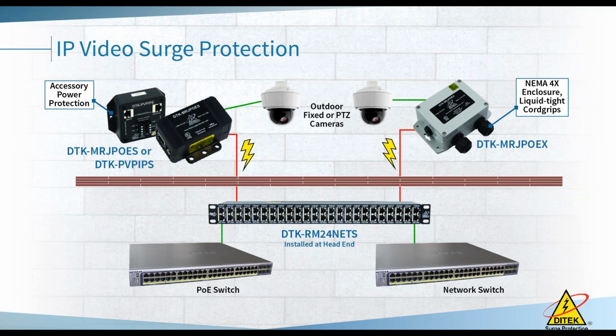The S version still accommodates plastic RJ45 and unshielded cable, but if you're running shielded cable, you now have surge protection at both ends without needing to ground the surge protector at the camera end, which can be tricky—finding a good ground and keeping it tamper-proof is a real pain in the field. Since you can't ground the shield on both ends anyway with shielded cable, this version references shield on one end and gives shield ground on the other, taking all surge protection to ground at the head end. So let's start using the S version.